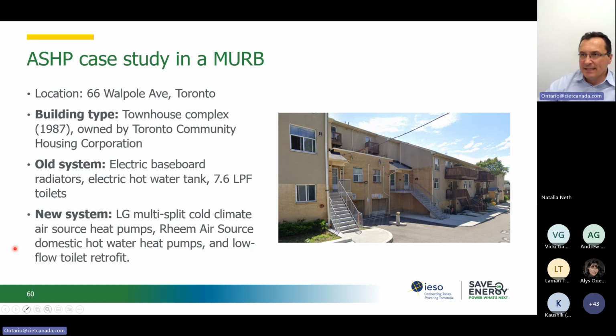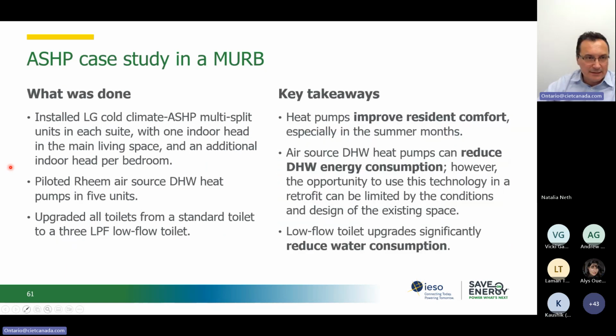That's an example of an air source heat pump system in a low-rise multi-residential building. Because we had electric heating before, this has a reasonable business case to support it as well. So not only the energy efficiency, but also we see some savings on bills. Looking at this, you can see that we addressed more of a deep retrofit in this building, beyond just one system. We looked at domestic hot water as well.